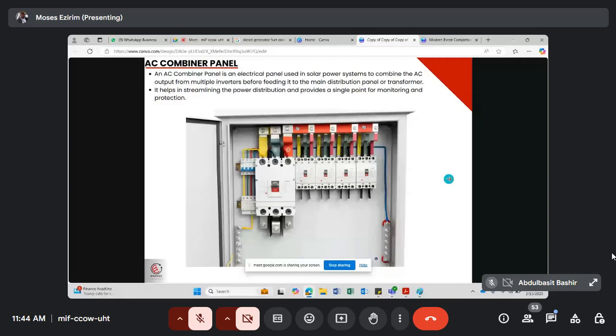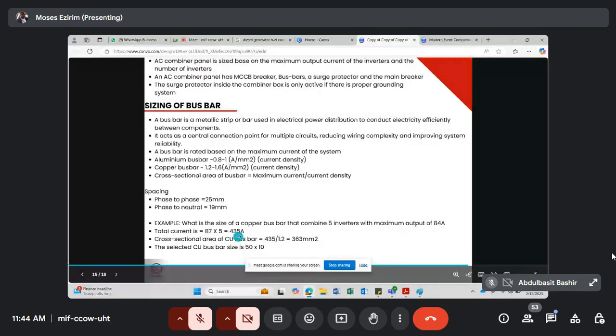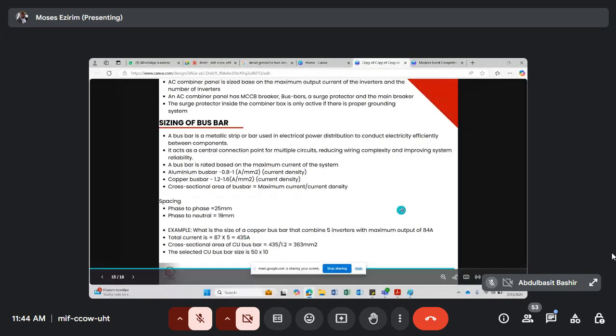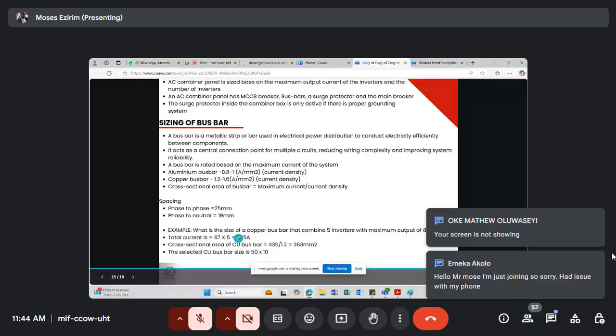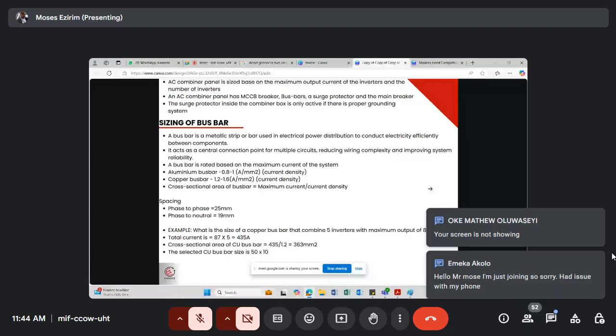Now let's see the copper bar. Combine 5 inverters, each with a maximum output of 87 amps. This is it. The total current, since it's 5 inverters, is 435 amps. So that is what I need. If you can't see it, you go for higher ones. All right. Now, even if I know the rating of the bar, how do I size it?